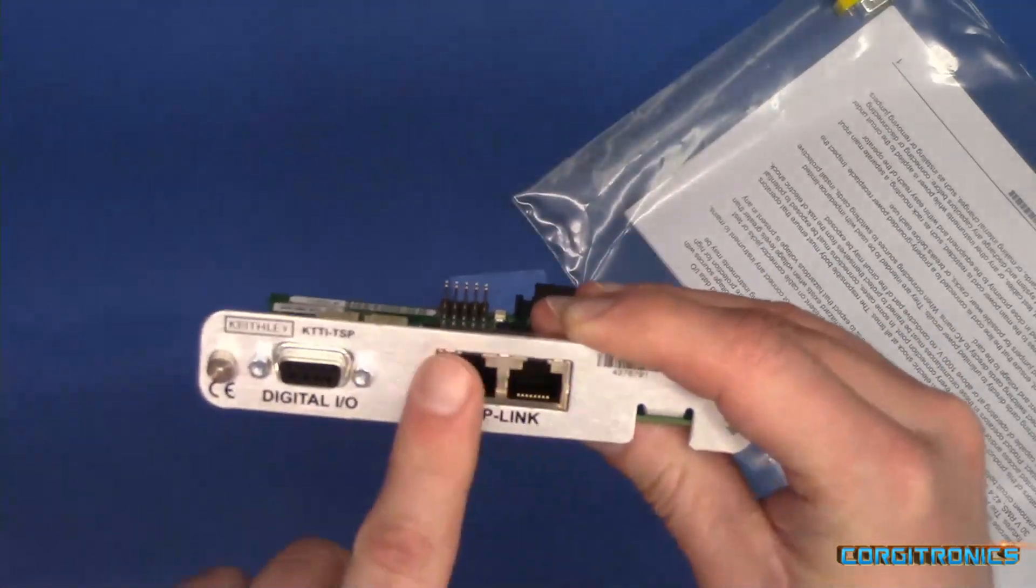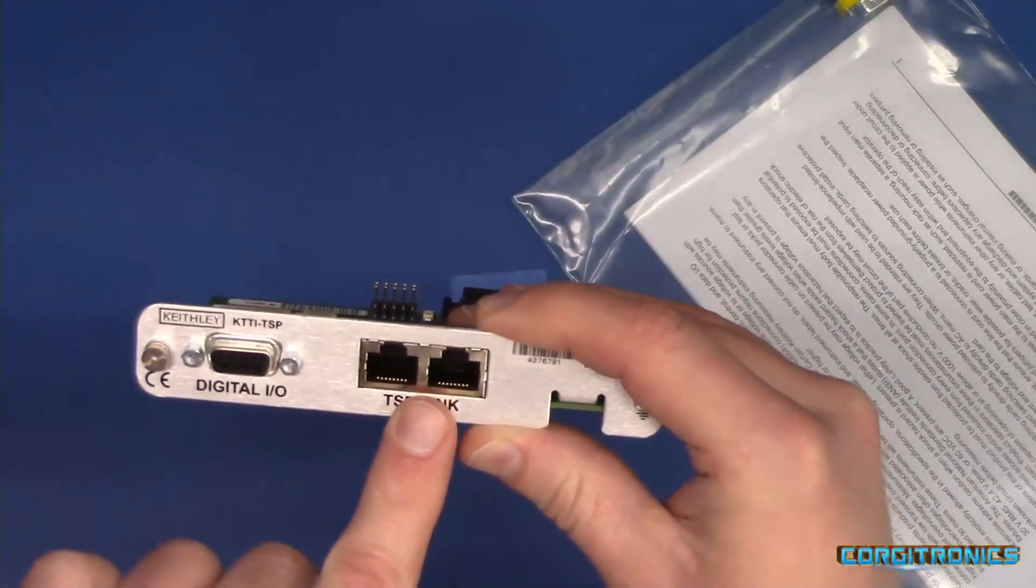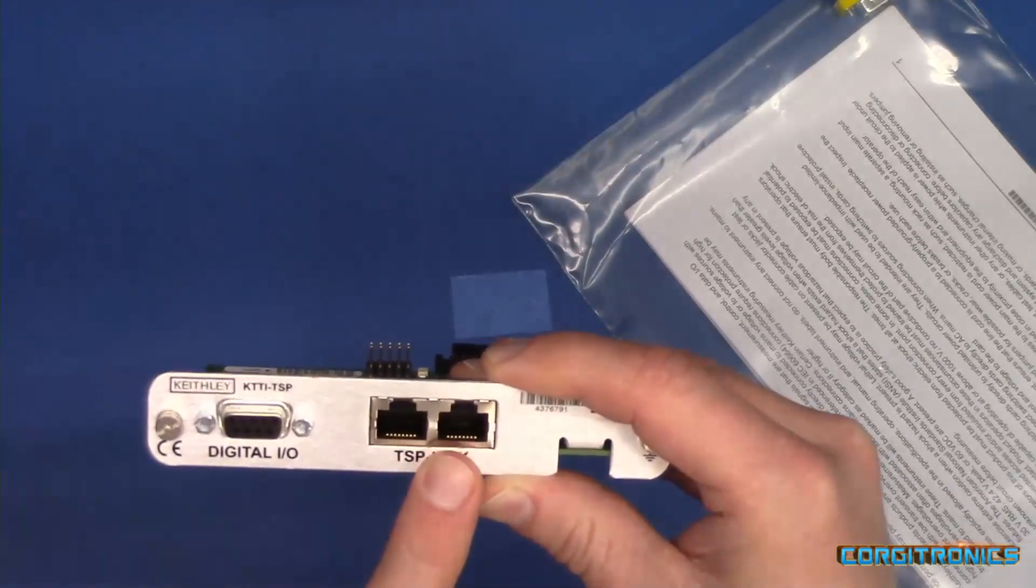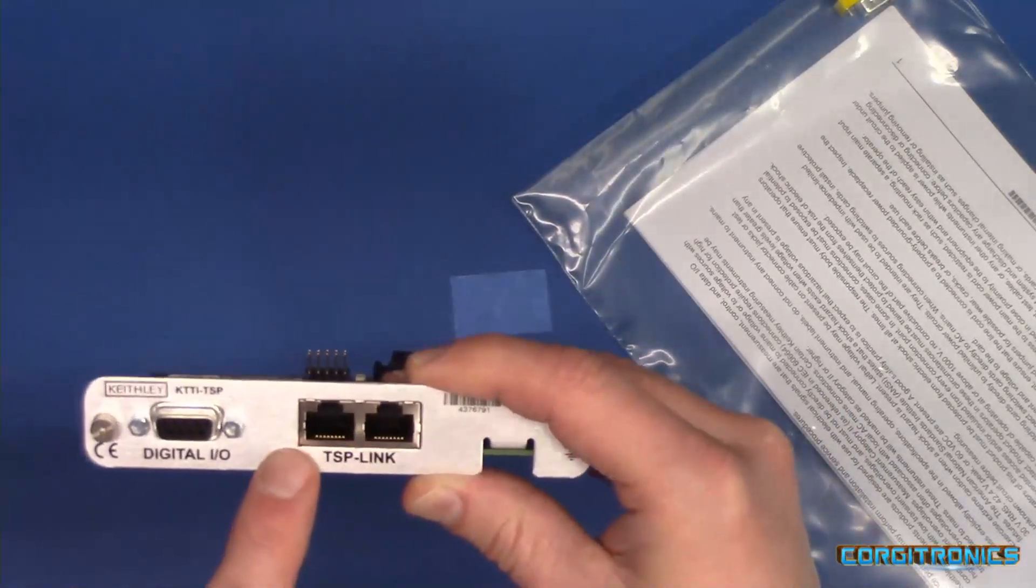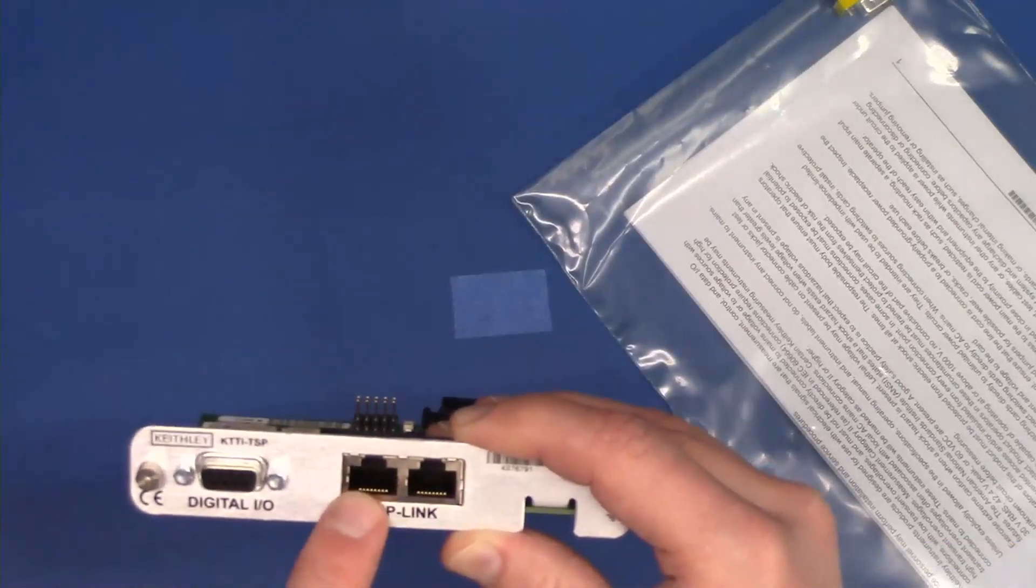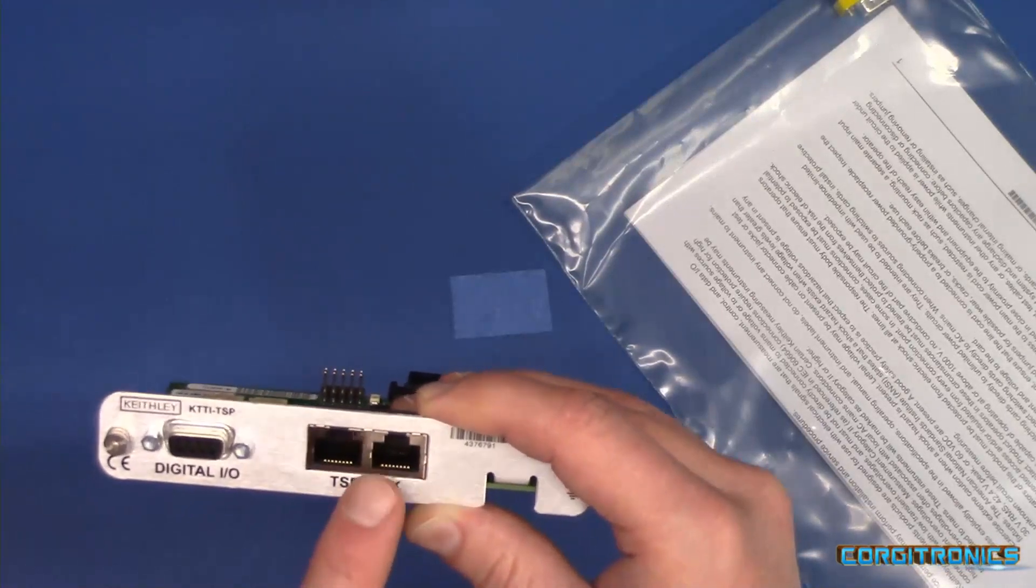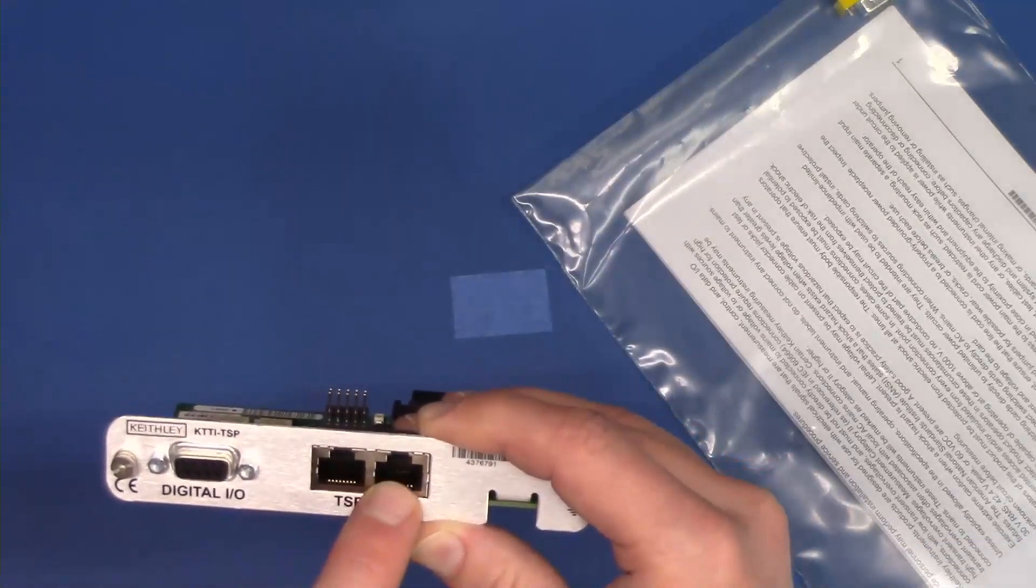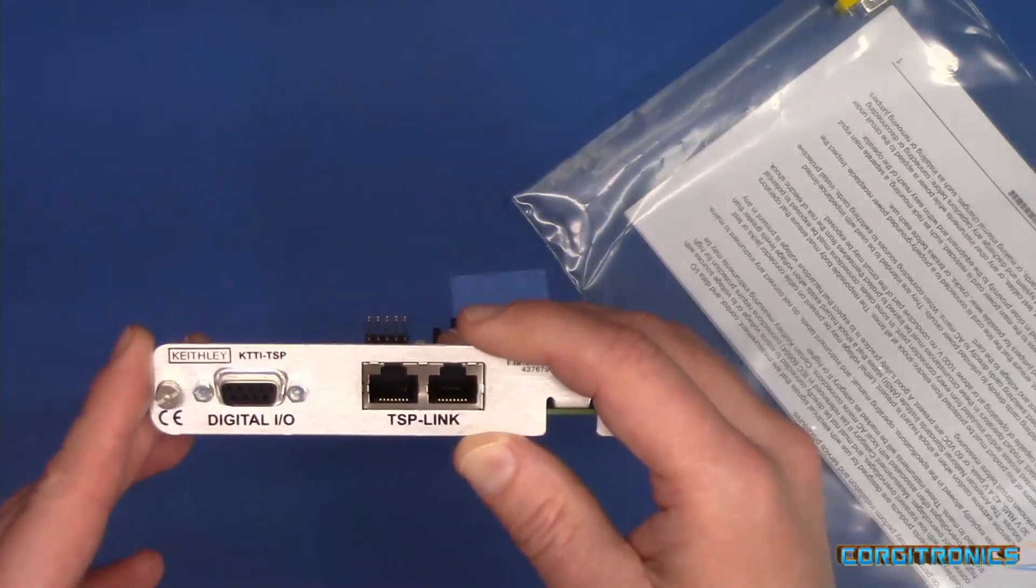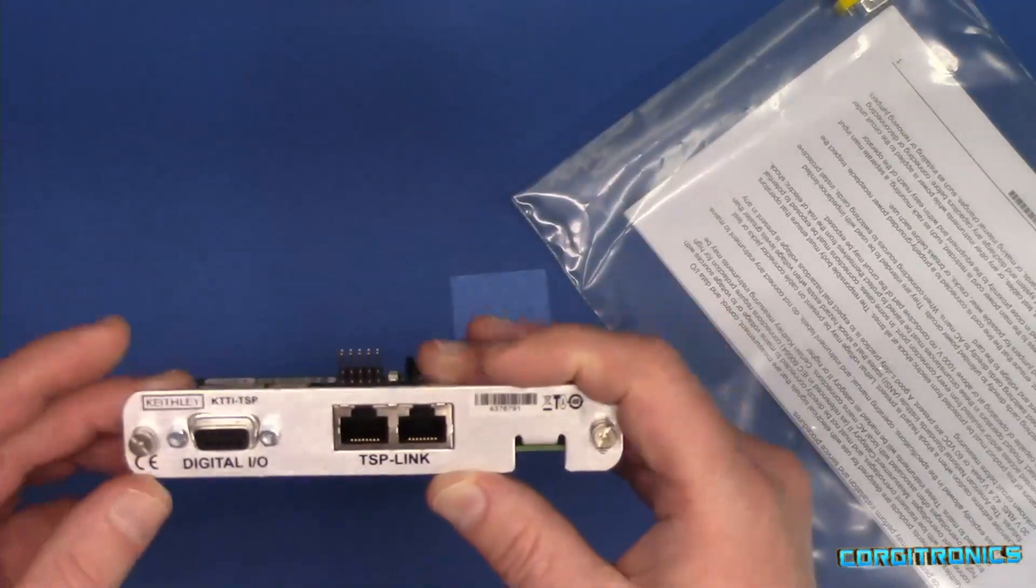So it has two connections for in and out. You can loop through. It doesn't really matter which goes on there. But the various high end, higher end Keithley units like the source measure units and the DMM 7510 have TSP link. And that's a proprietary protocol that includes not only full duplex communication through a bus, but it also has, as I recall, trigger wire trigger lines in here as well. And what it does is it allows one meter to control another meter or other devices. And if you've seen some of my other ones, I had one source measure unit controlling a meter. And so we can do the same thing with this.